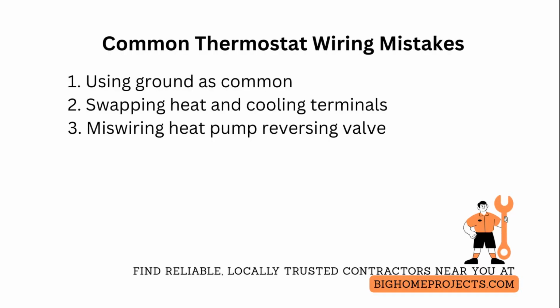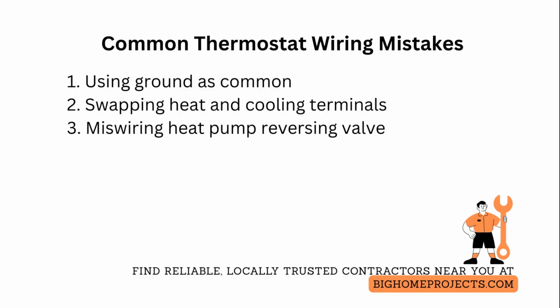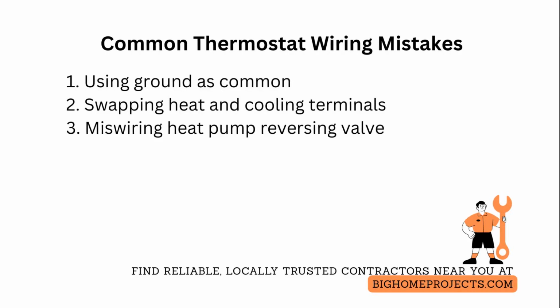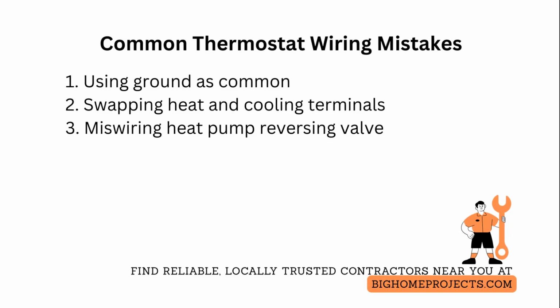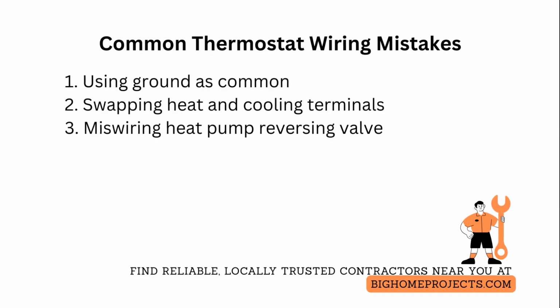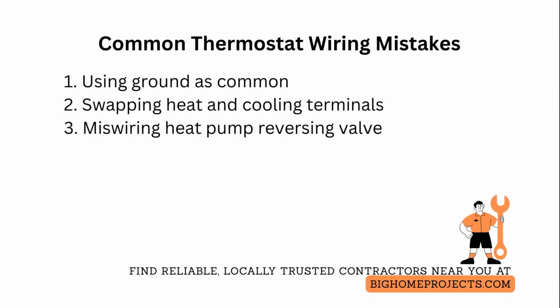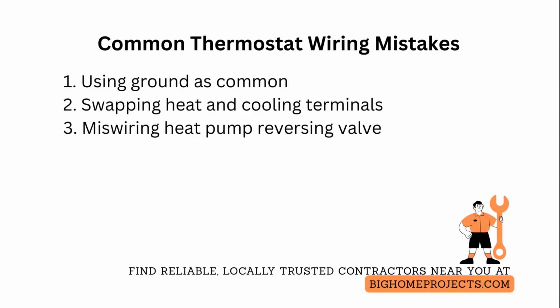Fix this by tracing the wire to the transformer's C terminal and confirming continuity, or using a voltmeter between R and the suspected common. Another common issue is swapping cooling and heating terminals, which results in the compressor or gas valve running at the wrong time. Remedy by matching each wire color and label to the furnace control board and testing each function before finishing the install.